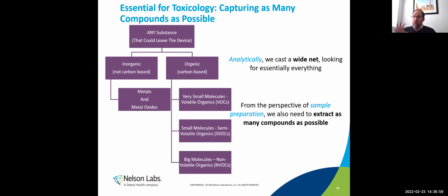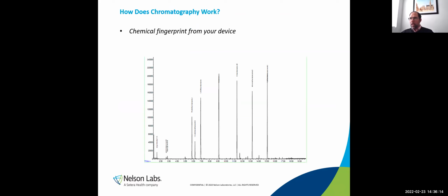If we can justify just running a portion of the full E&L, or maybe one of the other tests I mentioned before, to mitigate the risk, that's what we tend to look for. Extractables and leachables are very expensive and long, so we try to stay away from automatically going to those tests. But E&L does give you a good chemistry fingerprint of your device.